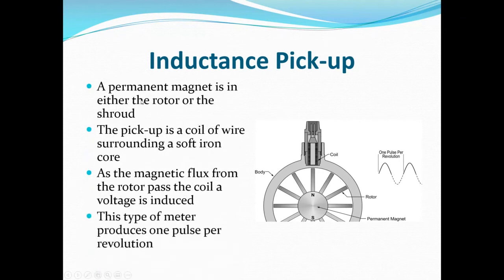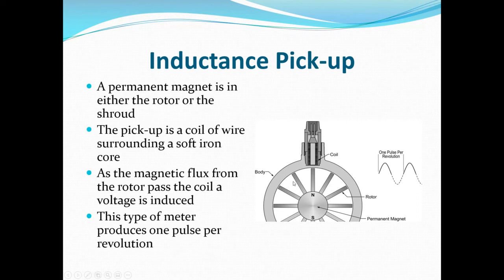Inductance style pickup: the permanent magnet is in the rotor or shroud — the spinning part. The pickup is a coil of wire surrounding a soft iron core. The flux from the rotor passes through the coil and voltage is induced. This type produces one pulse per revolution — there is a single magnet at one point on the fins or shroud, and every time it comes around, it gets counted once. That's the big difference: reluctance counts every blade, inductance counts once per revolution.